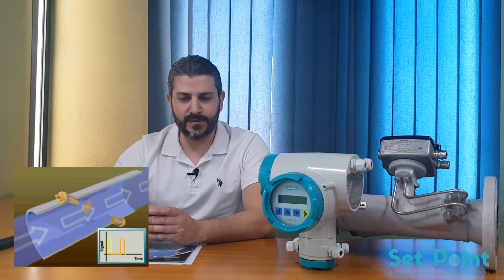Doppler flow meters are often used for flow measurements of fluids such as slurries. Transit time ultrasonic flow meters measure the difference in time from when an ultrasonic signal is transmitted from the first transducer until it crosses the pipe and is received by the second transducer. A comparison is made of upstream and downstream measurements. If there is no flow, the transit time or travel time will be the same in both directions. When flow is present, sound moves faster in the same direction and slower if moving against it. Now let's have a deeper look at both technologies by Siemens itself.